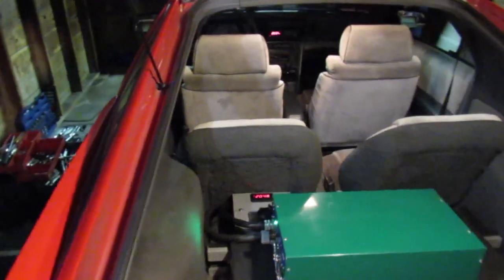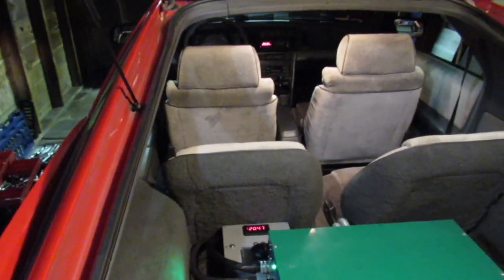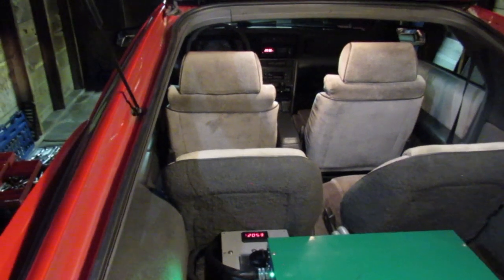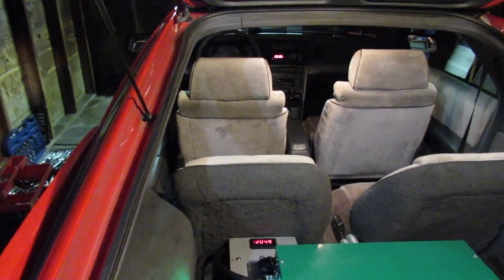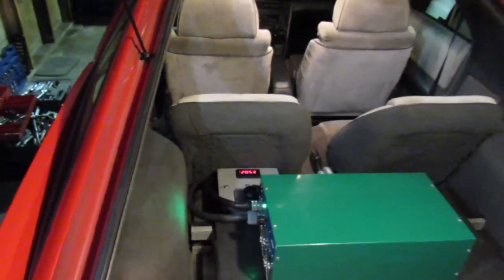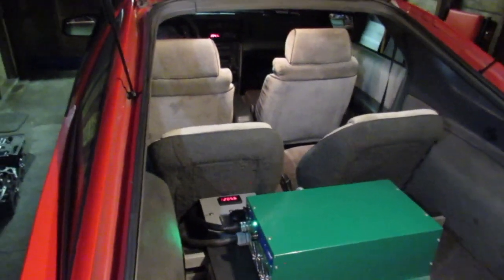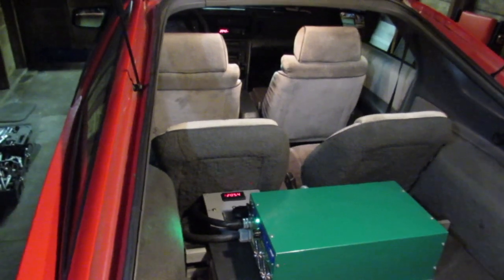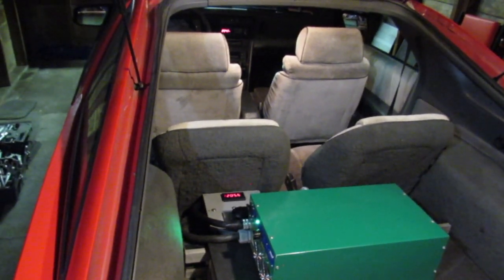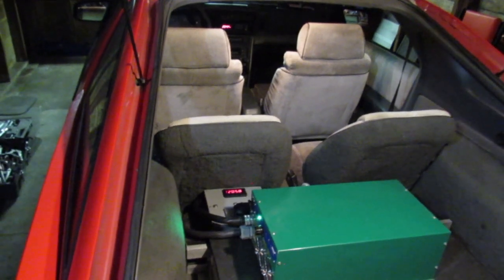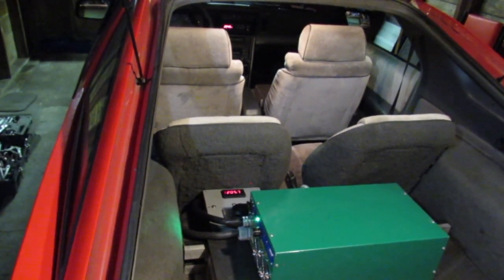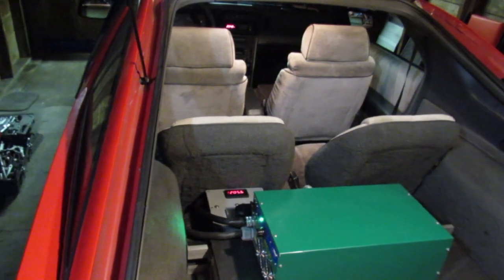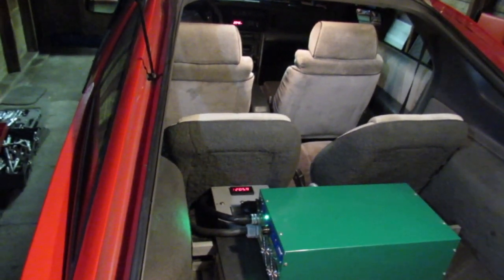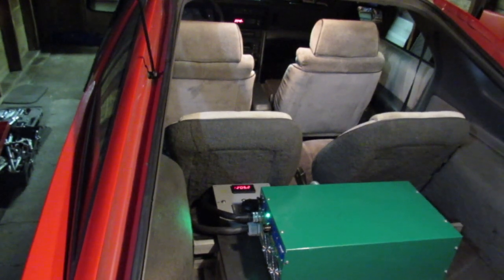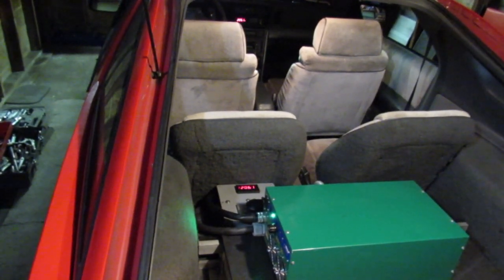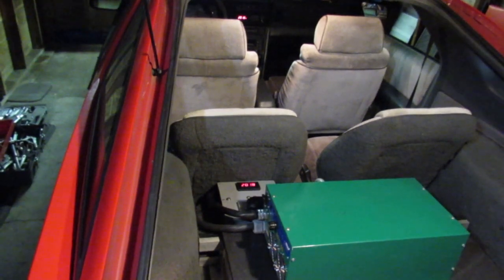So when the charger buddy gets to 206.5, which I believe was our set point, it's going to turn off our charger. If I can get the charger and the JLD and this all in the shot at the same time without too much shaky cam - so we're at 205.6, 205.9. You see the voltage kind of goes up and down. That's normal as the charger gives it a little more juice and then lets off a bit. And there it is, 206.5.